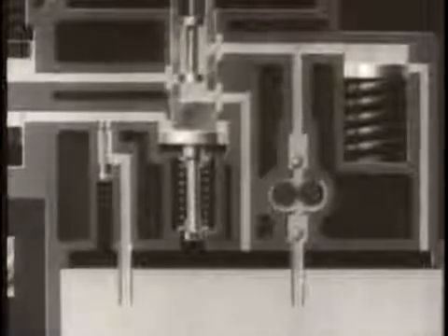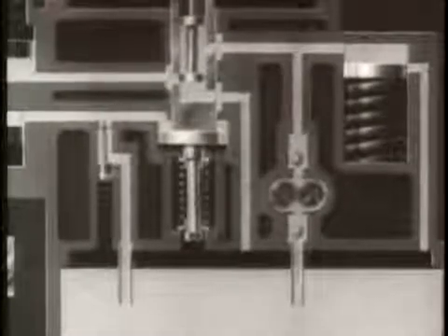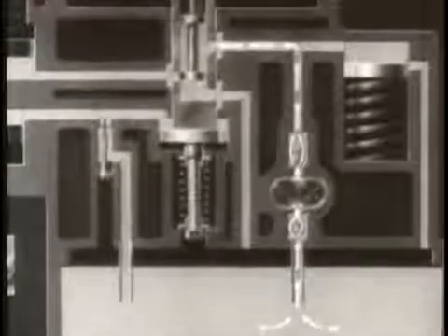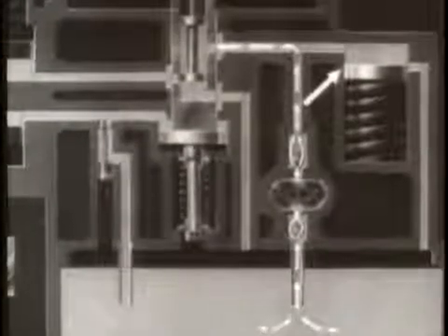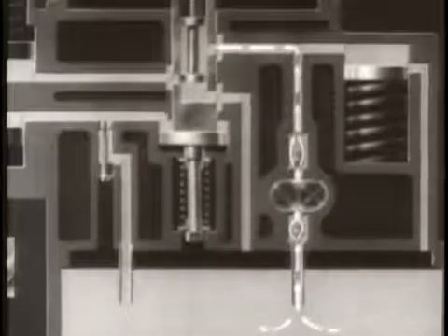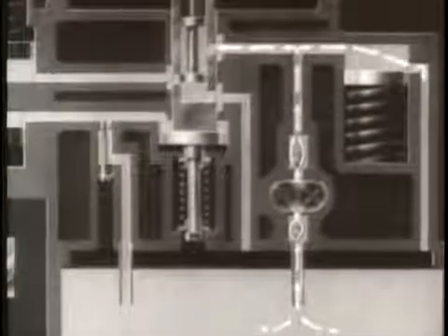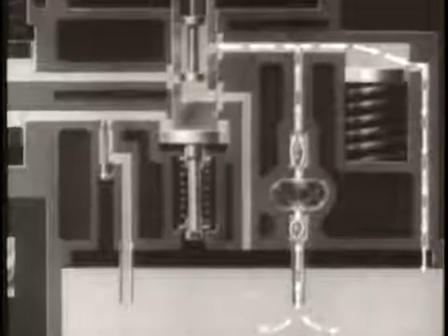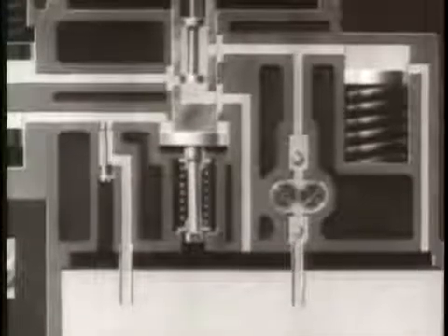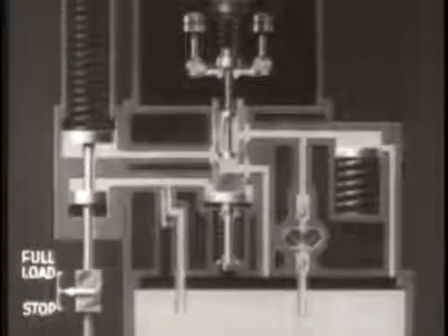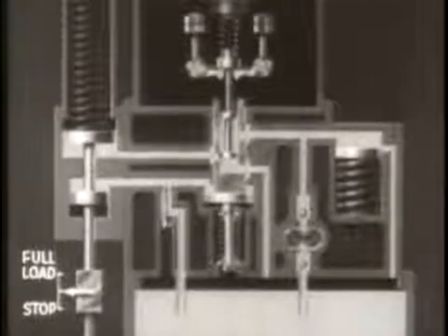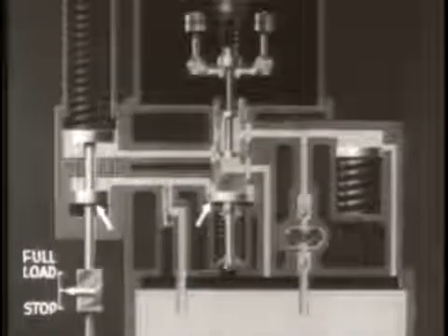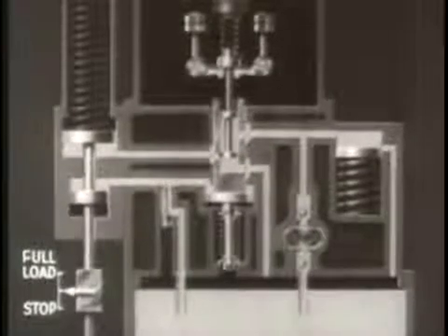The gear pump, which supplies the high-pressure oil, is driven from the governor drive shaft and takes suction from the governor oil sump. A spring-loaded accumulator maintains a constant head of oil and allows excess oil to return to the sump. To increase the regulating governor's sensitivity and to prevent overcorrection, a compensating mechanism is used.